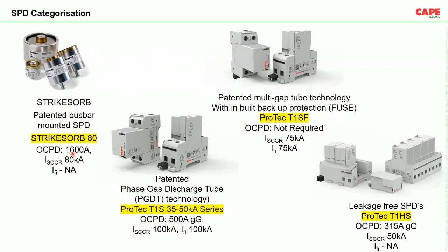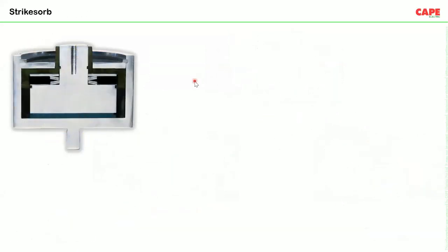What I wanted to show you is the safety parameters, because in all our seminars, we talk more about safety than other parameters. So for safety, this device has a backup protection of 1600 amps. The second device has a backup protection of 500 amps. The third device does not require any backup protection. The fourth device requires up to 315 amps. So, so many types of SPDs are available in the market. When you buy or select a type 1 SPD, you must understand your application and select the SPD appropriately. That is what I wanted to explain. Same performance, same impulse current, but different parameters are available.